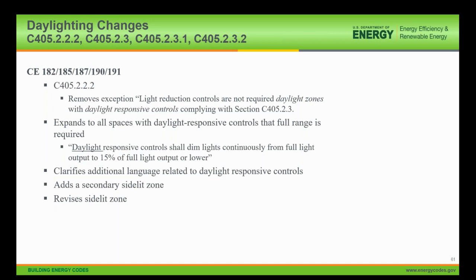It also, with some of the daylighting changes, expands the continuous full range of dimming. Previously, the IECC only had a handful of spaces where you're doing daylight dimming. Those spaces had to have full continuous dimming down to 15%. Now this says all the spaces where you're doing daylight dimming should have that full continuous dimming. That's really based on the shift from fluorescent to LED, which allows for continuous dimming much more easily than the way we used to do it with fluorescent. It also clarifies some language related to daylight responsive controls.